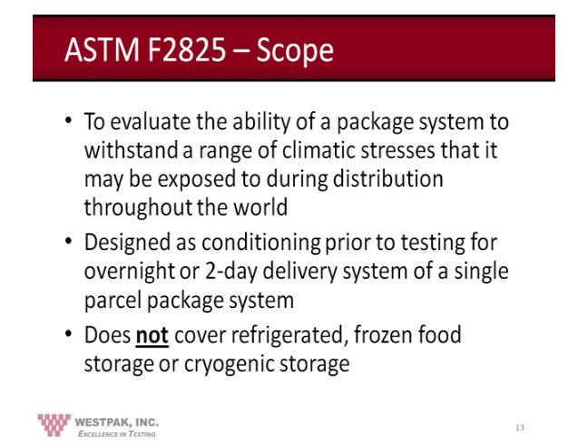ASTM F2825 evaluates the ability of a package system to withstand the range of climatic stresses that may be encountered during distribution throughout the world. It's important to recognize that the conditioning environment for overnight or express delivery of a package system is really no different from that of a standard parcel. The difference is that there are typically fewer packages exposed to this environment, which allows for quicker equilibrium of hygroscopic materials — specifically paper, paperboard, and corrugated — to conditions such as high humidity, which affects their strength.